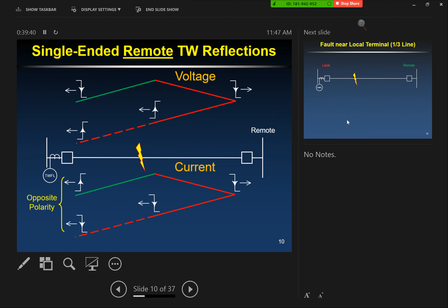So let's put this together to see what this would look like in an actual event. Let's see what this looks like if we have a fault on a third of the line, on the first half. What does that look like in terms of reflections? I'm putting my three points of interest as the local terminal, fault location, and remote end, and now we're taking advantage of that Bewley lattice diagram, charting the path these waveforms take with time on the vertical axis.